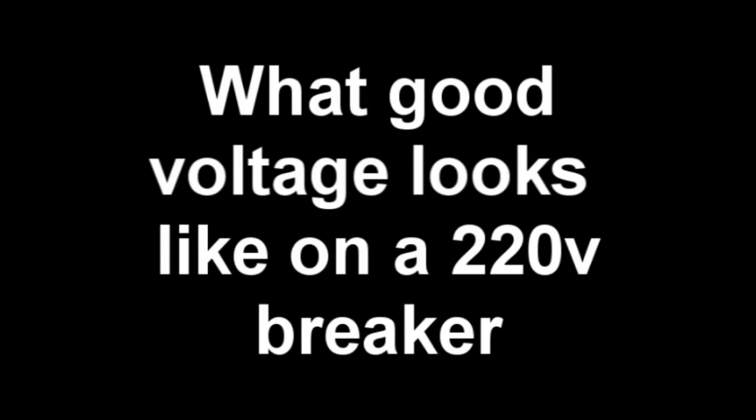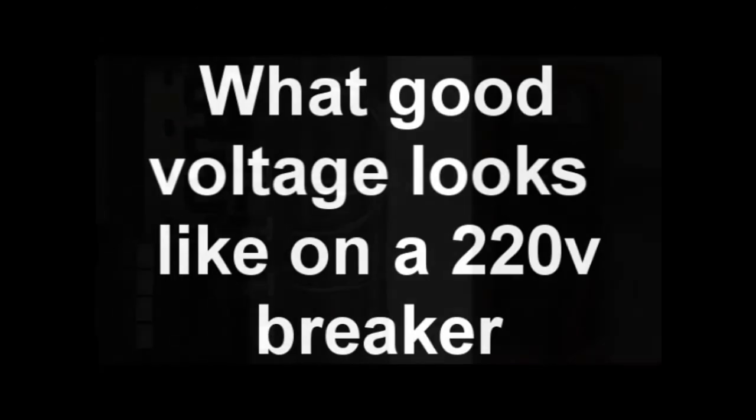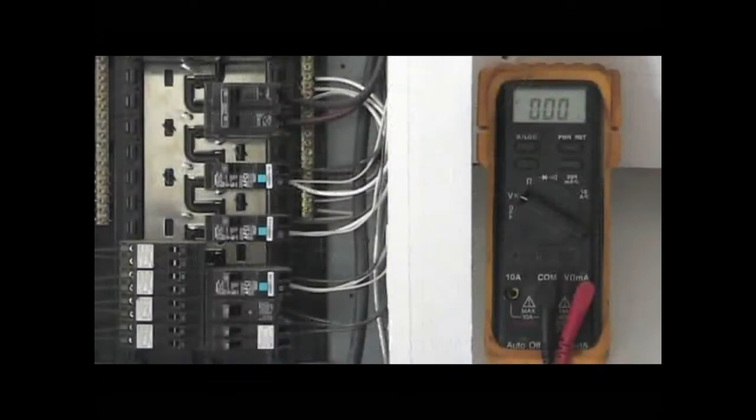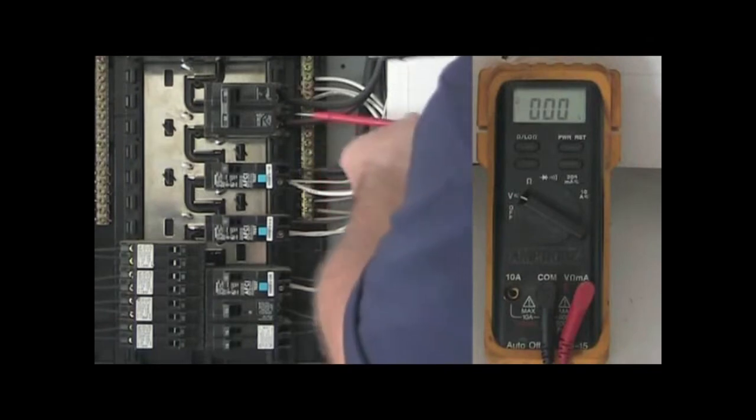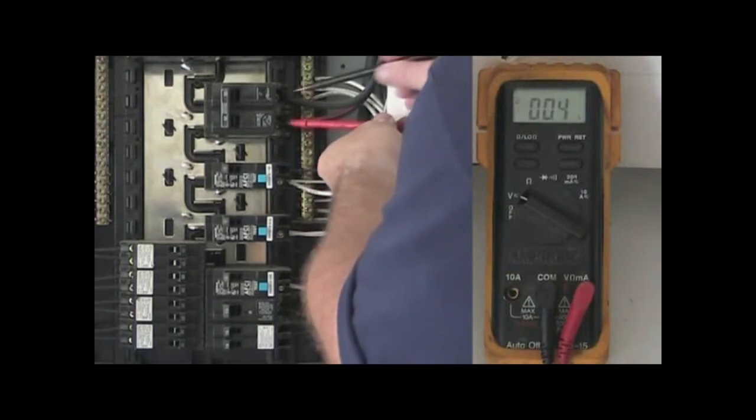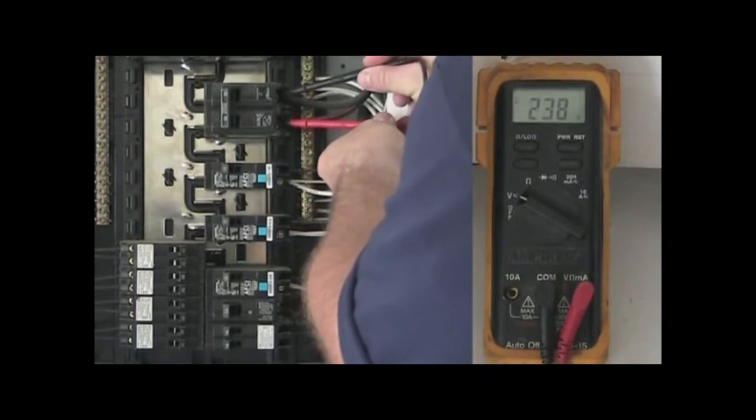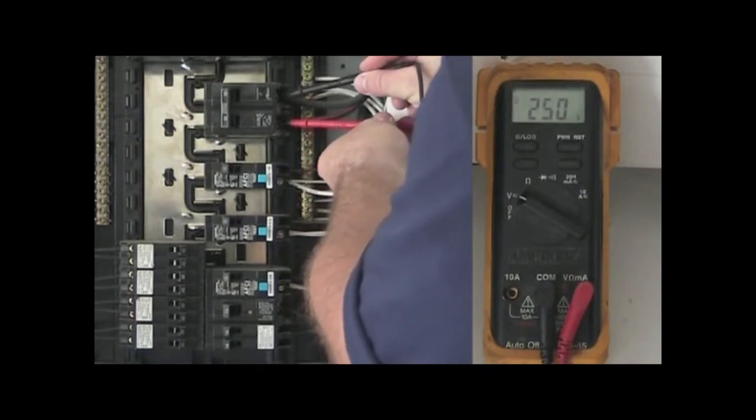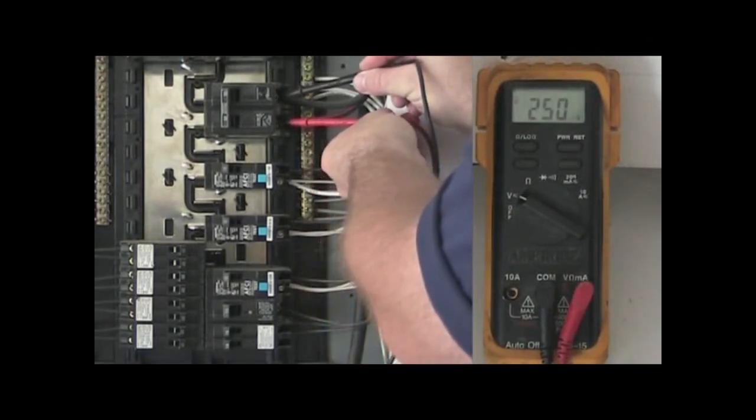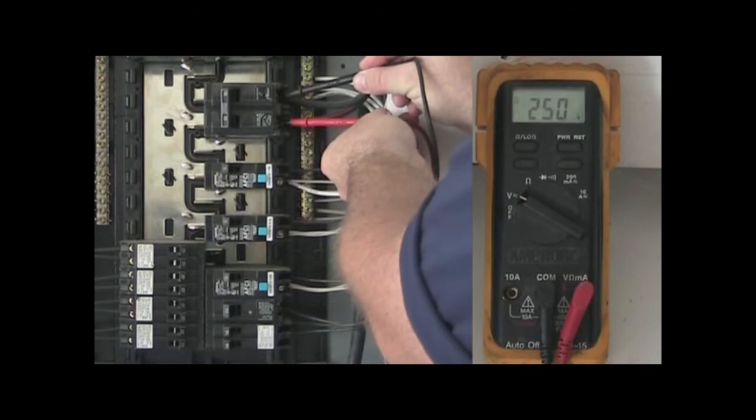For this test, both leads will connect to the breaker terminals. Polarity is not a factor, so it will not matter which lead connects to which terminal. If the breaker is good, it will read between 220 and up to 250 volts.